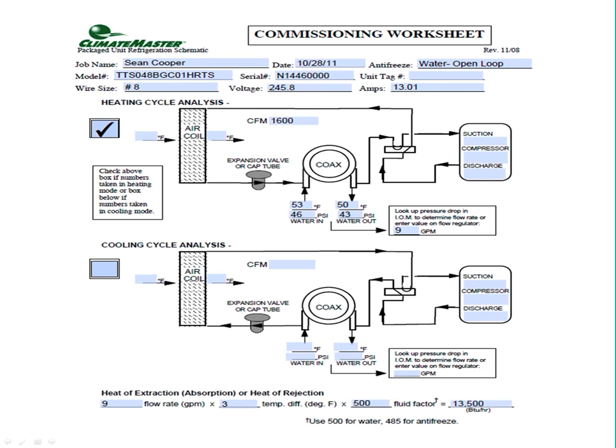If you did a performance startup sheet, you may have some comparisons. I always did that. I made sure I did a startup sheet. That was part of my job folder. Sometimes I left it on the job site with the paperwork of the heat pump so that I could tell what it once was and compare it to now. So again, I'm going to bring out that bucket and those hoses and that pump, and I'm going to circulate that cleaning solution through the coax.